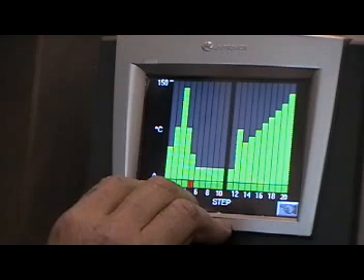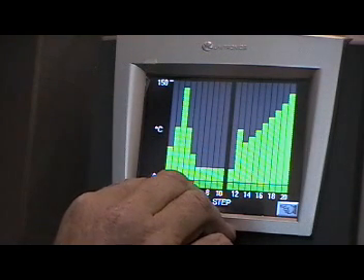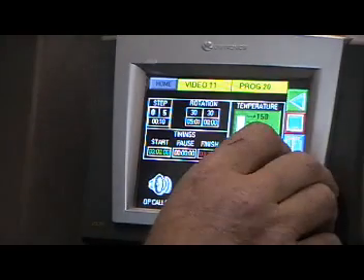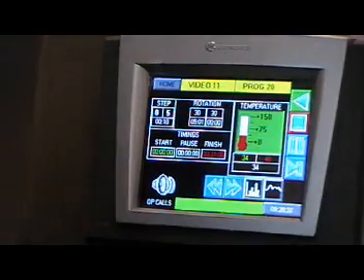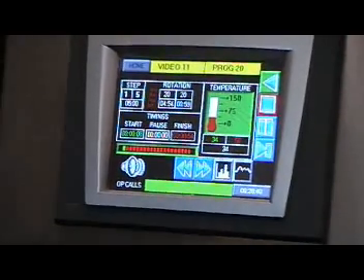It shows that we've got video 11 here. As a quick check, we can look at what we've programmed, the temperature up and down, and it's going to end at that point. So all these steps are negated. Back to there, press start. Can't press start without the lid now. Once it starts, it'll follow that profile.